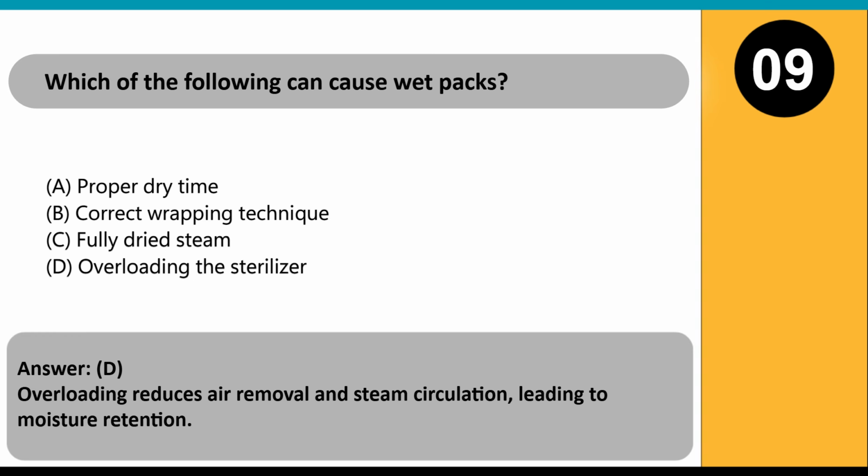Which of the following can cause wet packs? A. Proper dry time. B. Correct wrapping technique. C. Fully dried steam. D. Overloading the sterilizer. Answer: D. Overloading reduces air removal and steam circulation, leading to moisture retention.